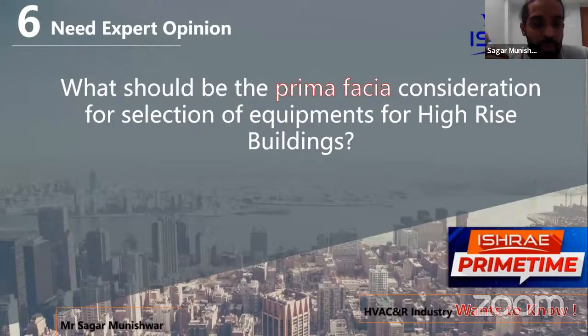What comes of primary importance is your pumps. Do we have pumps which can take care of high-rise buildings? Yes. Since firefighting is an open system, you need a pump which can develop more pressure, unlike an air conditioning system, which is a closed loop where the pressure to be developed is less. So we have pumps like multi-stage pumps and horizontal split casing pumps, which can deliver the required pressure with the given flow in a firefighting system. So do we have those pumps available? Do we have that system available?